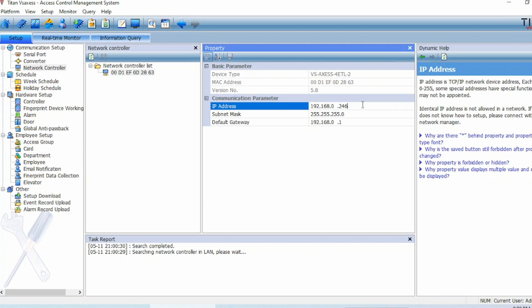You saw the two-door version earlier. In setting up, the four-door version is a little bit different. On the bottom right-hand side, don't forget to change your IP settings as seen in the two-door version. When you open Titan again, go ahead and click on Network Controller as before — it's going to find the four-door version. Be sure to change the IP address: for the two-door version, keep it at 245; for the four-door version, keep it at 246. Those are two totally separate IP addresses.